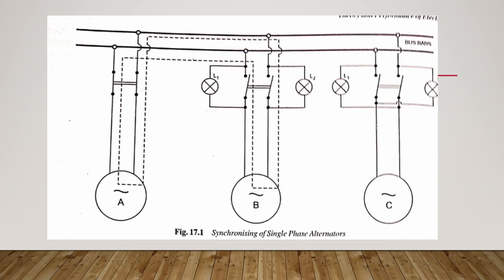If the frequencies of alternators A and B are exactly the same and their terminal voltages with respect to the local series circuit are in exact phase opposition, then no resultant voltage will act across the lamps L1 and L2, and therefore these lamps will remain dark. If the frequencies of A and B are not equal, the phase angle between their voltages will be continuously changing, and therefore the current through the synchronizing lamps and the local series circuit will change, resulting in flickering of the lamps. The frequency of flickering will be equal to the difference of frequencies of the two alternators. That is, the greater the difference in frequencies, the greater the frequency of flickering, and the lesser the difference, the lesser the frequency of flickering.